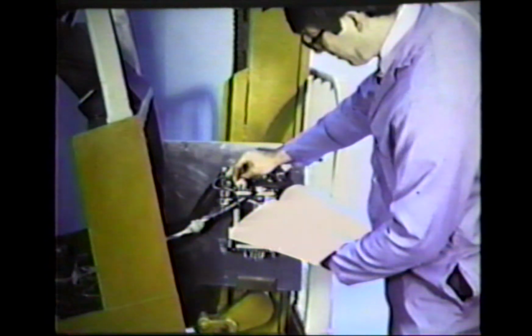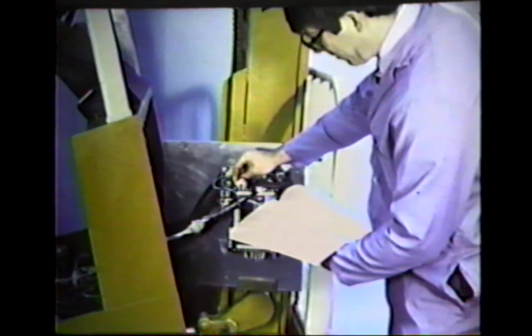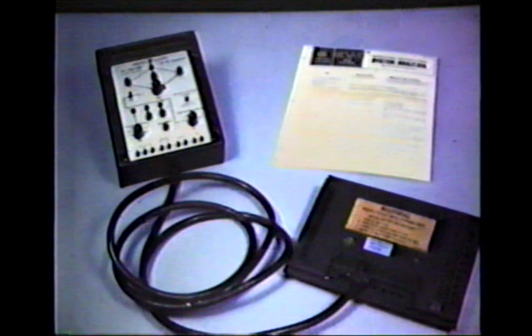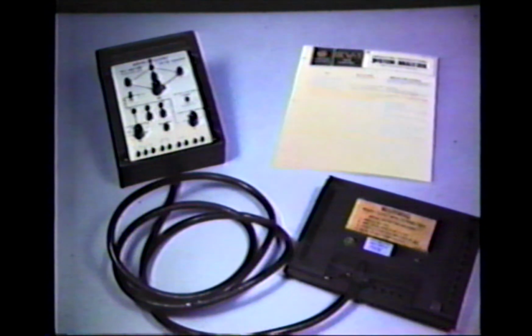As mentioned before, these are the most common symptoms of faults on the EV-1 control. Several other miscellaneous symptoms may occur, and these are mentioned in the troubleshooting guide of the Electrical SCR textbook. There is also an EV-1 Analyzer available, which can be used in conjunction with a volt-ohm meter to check out all circuits and components in the drive control except for the 4 rec. If everything checks good using the analyzer, then it is assumed that the card is bad.